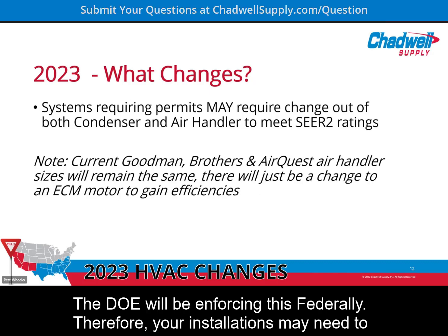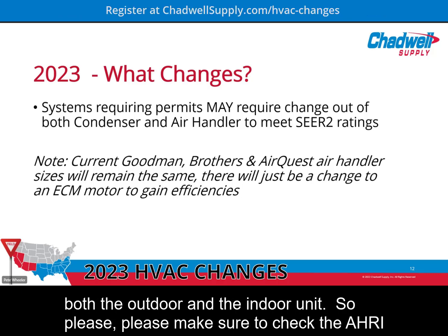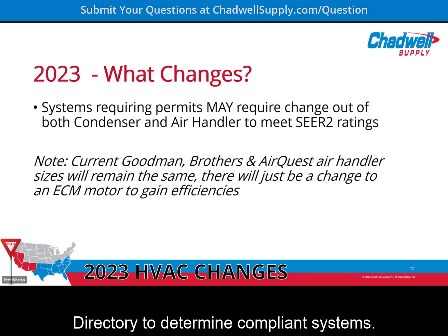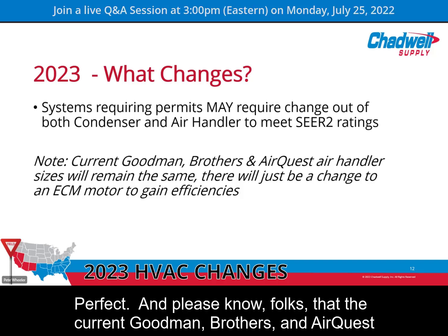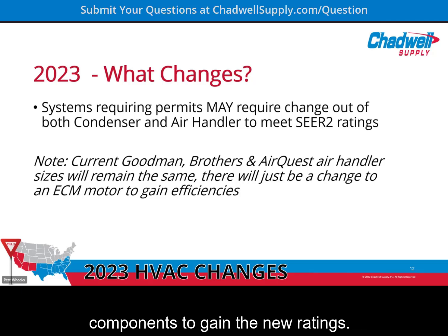The DOE will be enforcing this federally. Therefore, your installations may need to comply with the new 2023 minimum efficiency requirements, which may require changing out both the outdoor and the indoor unit. So please make sure to check the AHRI directory to determine compliant systems. Perfect. And please know, folks, that the current Goodman, Brothers and AirQuest air handler sizes will remain essentially the same. Those will have increased efficiency components to gain the new ratings.